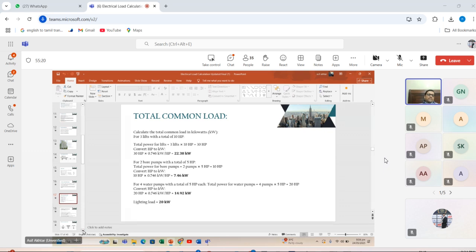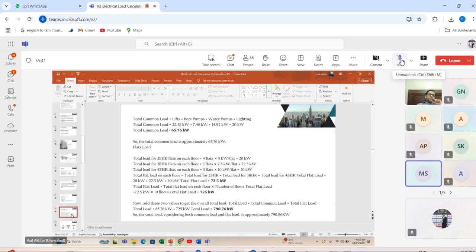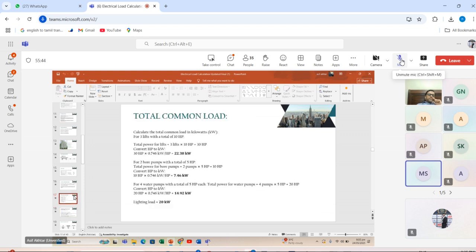Or do we have to manually count all the lights that we install there? Yes, you can also manually count the lights. For example, if there are hundreds of 10 watt lights installed, then we can estimate the total kilowatt load. Yes, you can also do this. On the other hand, you have the limitation of a 5 kilowatt load for a 2 BHK. If we don't have the limitations, then how can we calculate the total connected load? We have to count or sum all the kilowatts or watts we have installed in a particular flat or building.